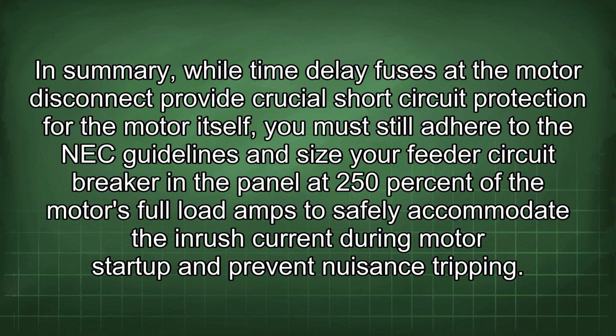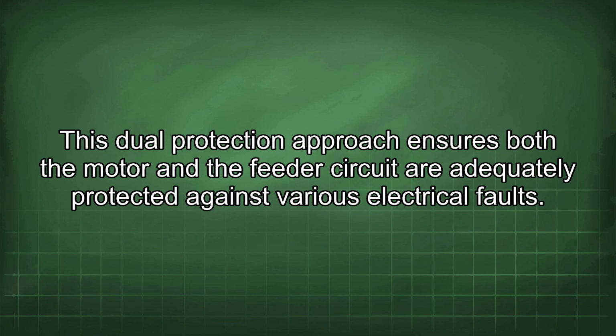In summary, while time delay fuses at the motor disconnect provide crucial short circuit protection for the motor itself, you must still adhere to the NEC guidelines and size your feeder circuit breaker in the panel at 250% of the motor's full load amps to safely accommodate the inrush current during motor startup and prevent nuisance tripping. This dual protection approach ensures both the motor and the feeder circuit are adequately protected against various electrical faults.